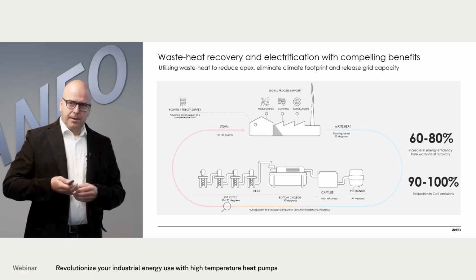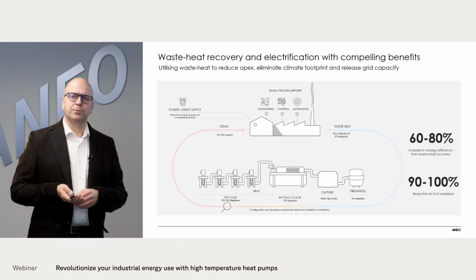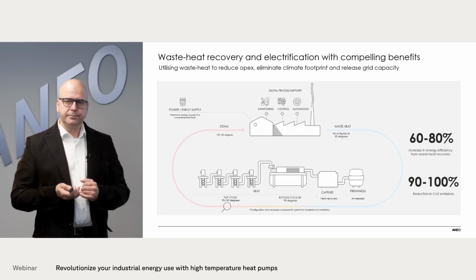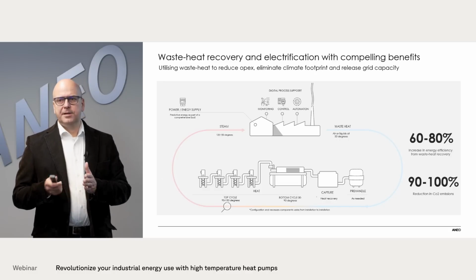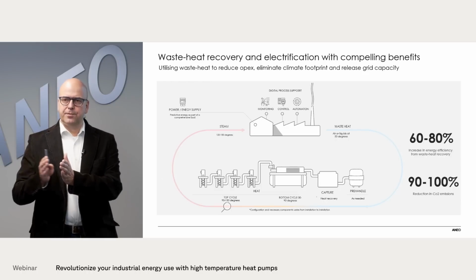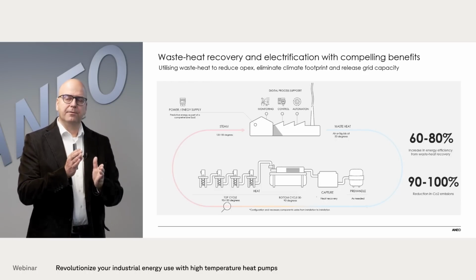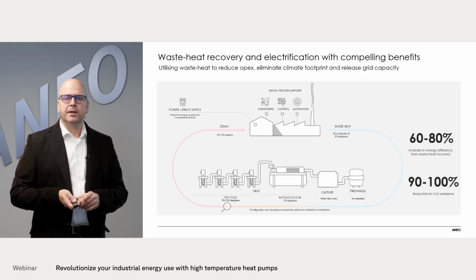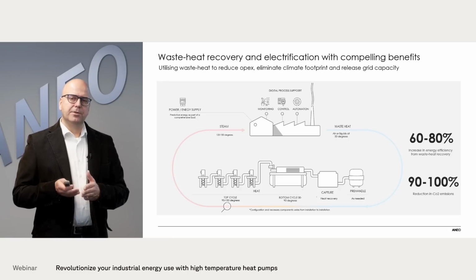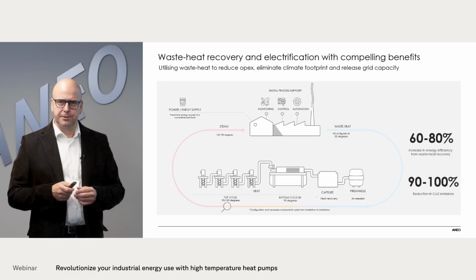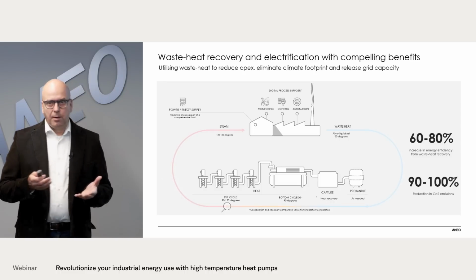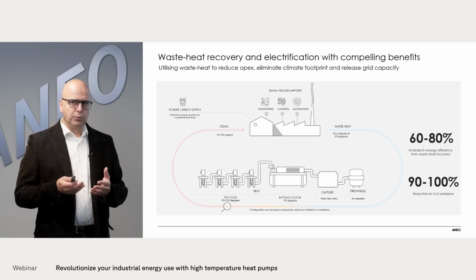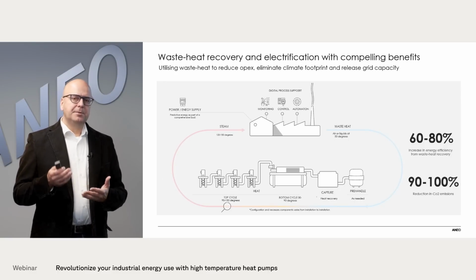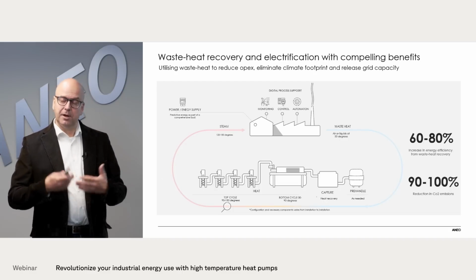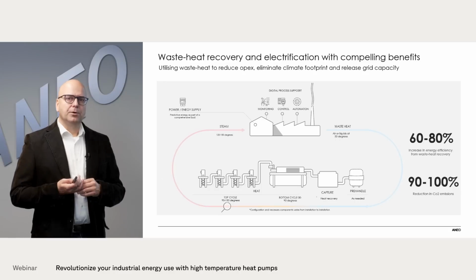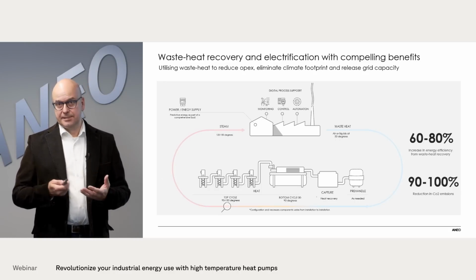However, once the heat is transferred to the bottom cycle technology, the bottom cycle produces steam at around 80 to 90 degrees out of this heat. The two main functions of the bottom cycle are, on the one hand, to compensate for variations in the waste heat temperature and to produce steam at a very constant and defined point between 80 and 90 degrees. From this point, we start to compress the steam up by a series of compressors. We can deliver steam up to 5 bars, so 150 degrees Celsius. However, in the factories we do in-depth integration. That means if the process only requires 1 bar or 2 bar steam at 120 degrees, we only supply this lowest possible pressure and temperature to the process in order to get the best COP out of it.